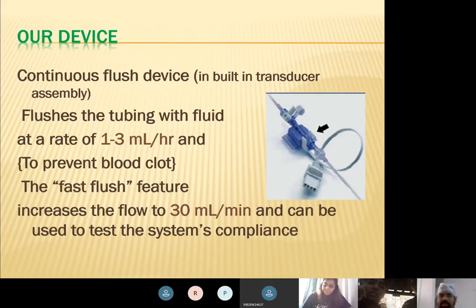Now, what else do we have? We also have something called a continuous flush device. That small blue colored thing that you pick up. When you open that, when you pull that up, it flushes the line. It flushes the line with fluid at the rate of 1 to 3 ml per hour. So if you keep on flushing it, it will just keep on giving fluid inside. So don't keep flushing that. You don't need a syringe to flush a line. Please understand this. You have a continuous flushing device which keeps on flushing fluid at the rate of 1 to 3 ml per hour.